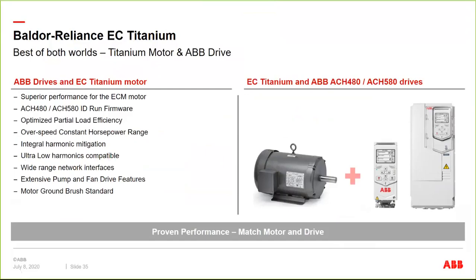Now, some of the other advantages you get with standalone drives is additional optimized speed and efficiency ranges. You can do more integral harmonic mitigation because there's ultra low harmonic versions of the product. More extensive range of networks. So again, I said we had serial Modbus and BACnet, but you can get Ethernet, Profibus, etc. with standalone drive and more extensive pump and fan features. So our basic controller comes with this, has basically 40 parameters on it.